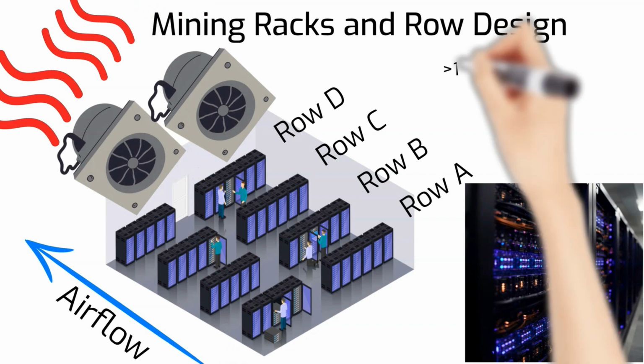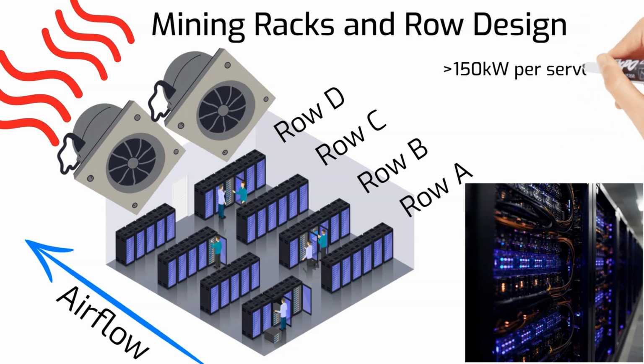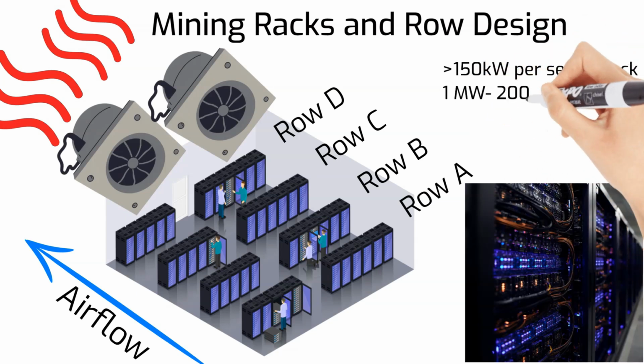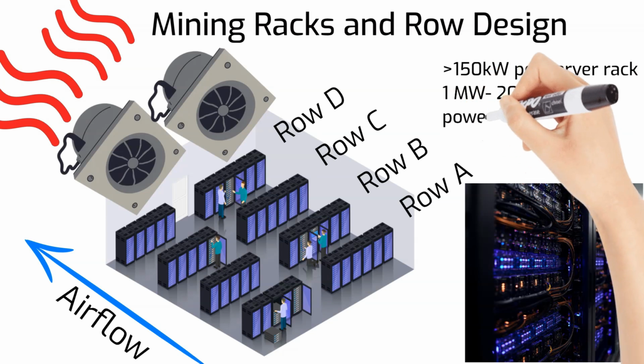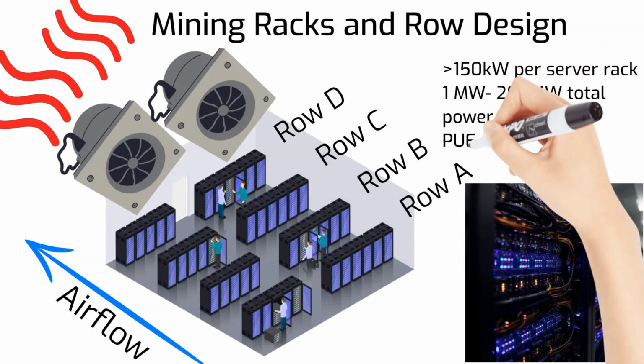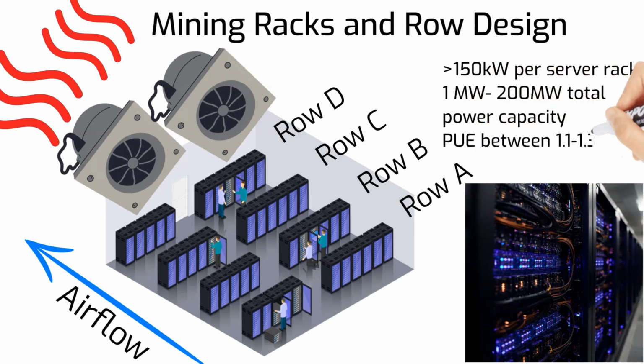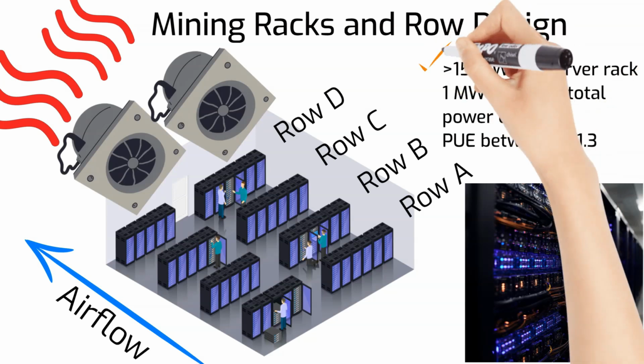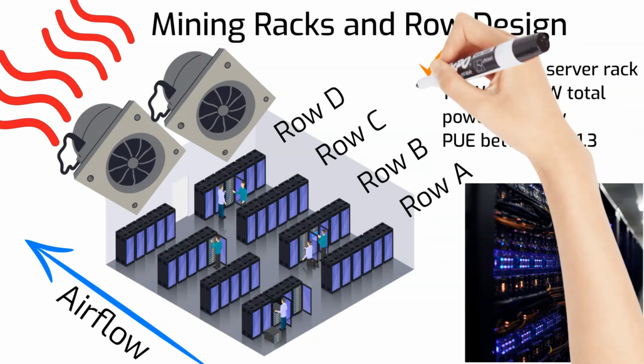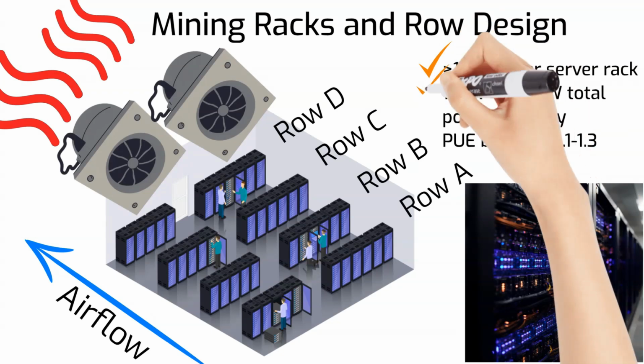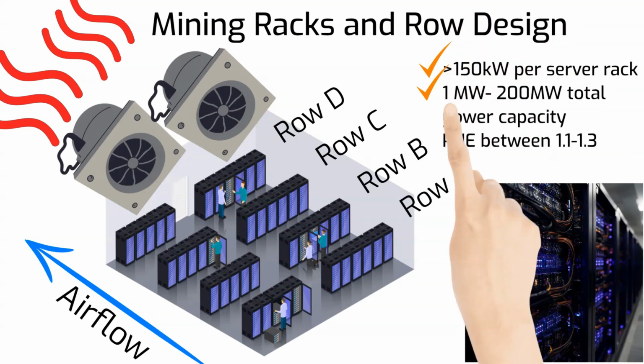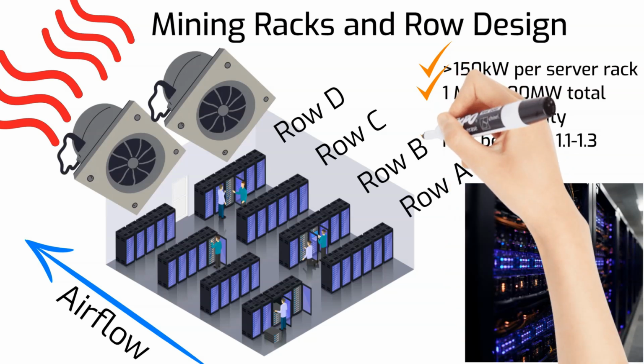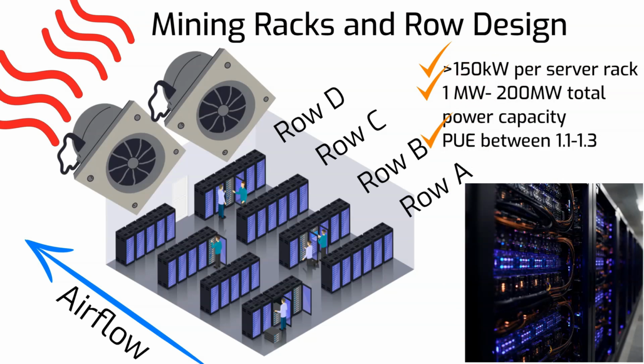Bitcoin mining operations have very high power densities, often exceeding 150 kW per rack in industrial settings. For high-density operations, liquid cooling, direct-to-chip or immersion, is more efficient, quieter, and allows for more compact layouts. Facilities commonly range from 1 MW, powering 300 to 900 miners, to large-scale operations consuming 200 MW. An efficient power usage effectiveness (PUE) for a mining farm is considered to be between 1.1 and 1.3. This means that for every 1.1 to 1.3 units of electricity consumed by the entire facility, 1 unit goes directly to the mining equipment.